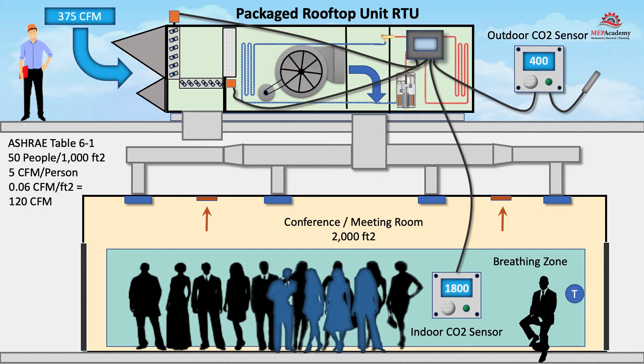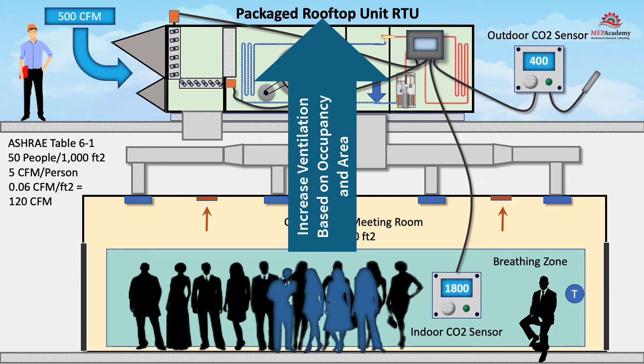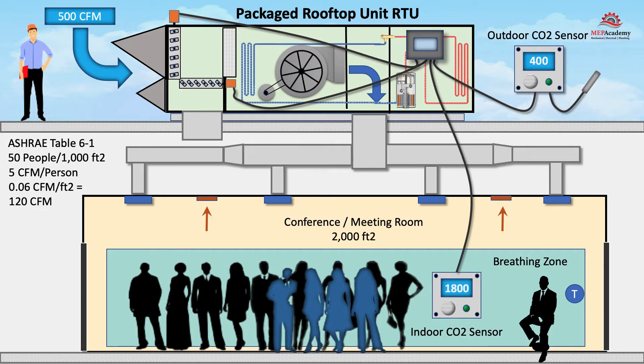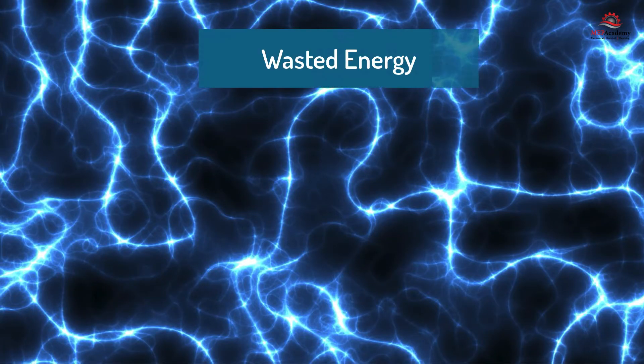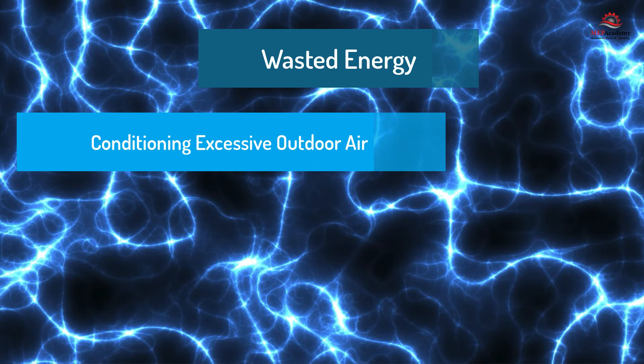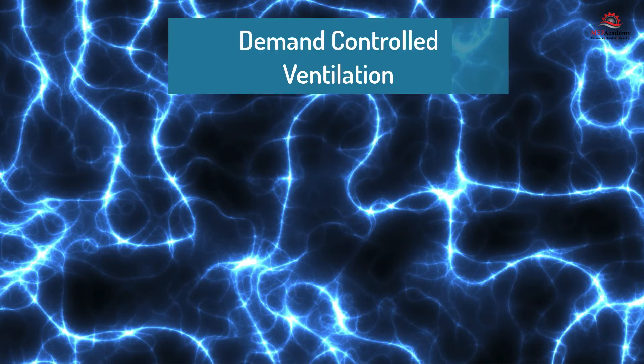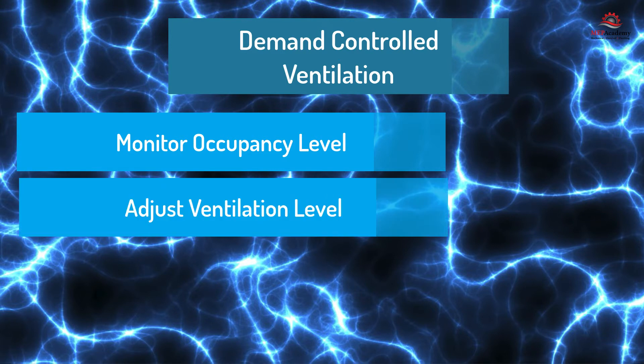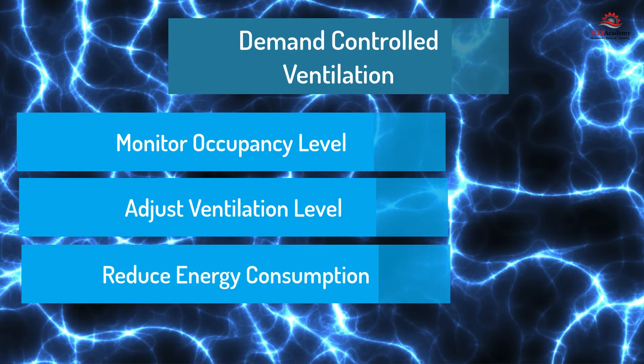With ASHRAE 62.1, the ventilation requirements or outdoor air is increased based on the number of occupants and square footage of the space. Demand controlled ventilation is based on providing outdoor air in proportion to the occupancy level. Energy is wasted in the form of conditioning excessive amounts of ventilation air when the occupancy level is less than the design maximum. By using demand controlled ventilation, the occupancy level can be monitored and the quantity of ventilation air adjusted downward according to actual occupant levels, not the design maximum.